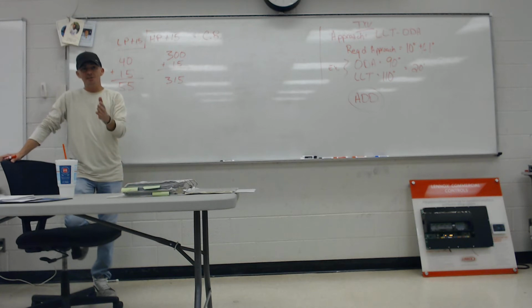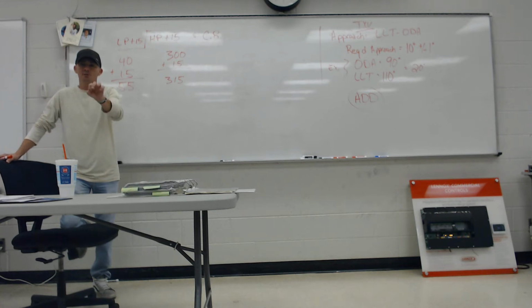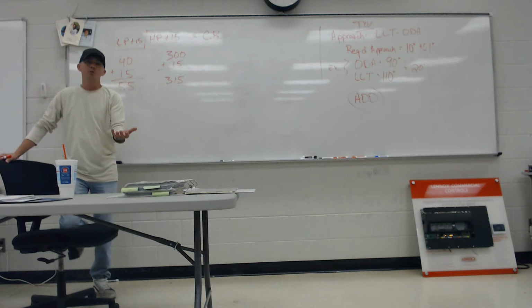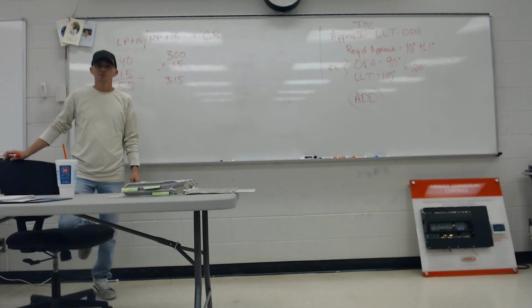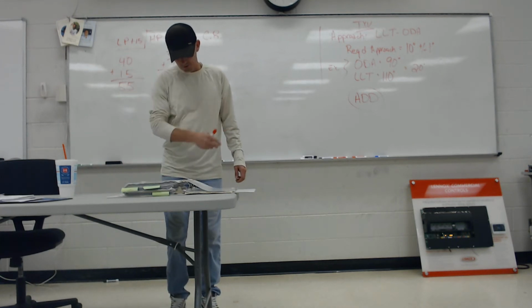And the reason we add 75 to it is, that's how much it just gives you a good idea. And guys, it's a guessing game, but it's a pretty good guess. When you add 75 to the discharge line temperature, that'll give you a good indication of what the oil temperature is on the cylinder walls or in the scroll set or wherever it really matters on the bearings. That'll give you a really good idea of what the actual oil temperature is, where it matters. Does that make sense? All right. Oil temp, moving on.